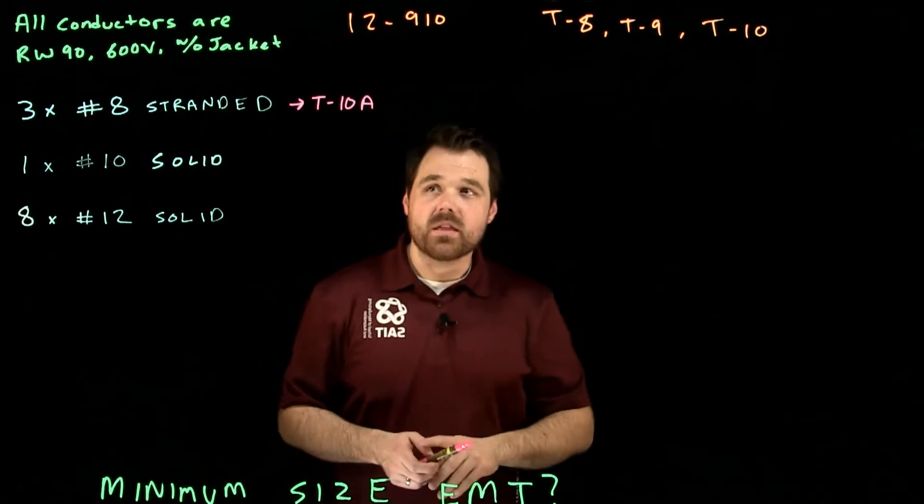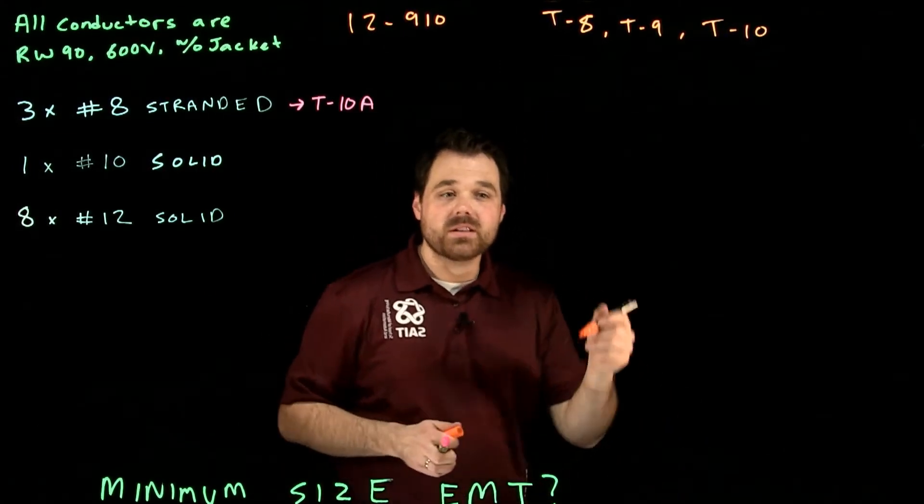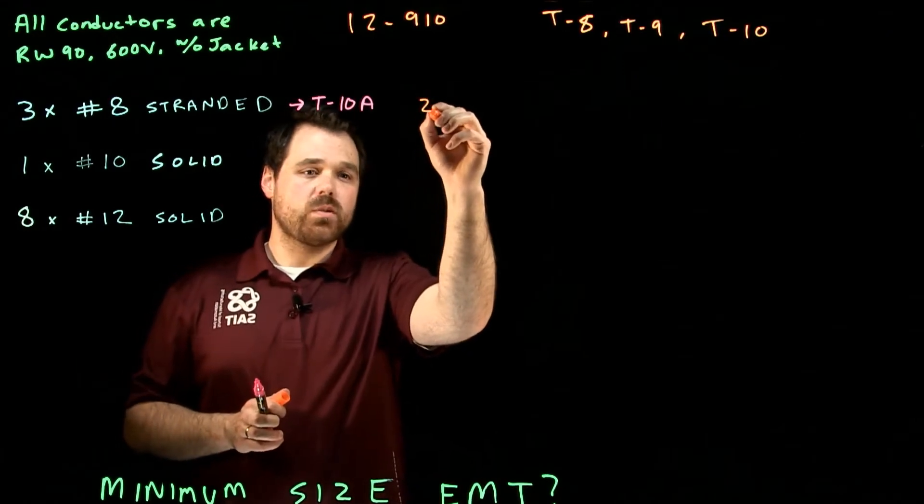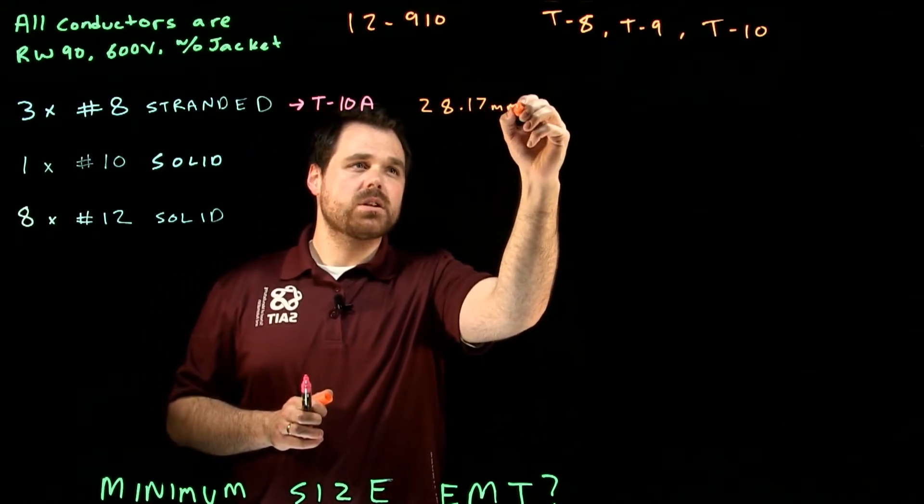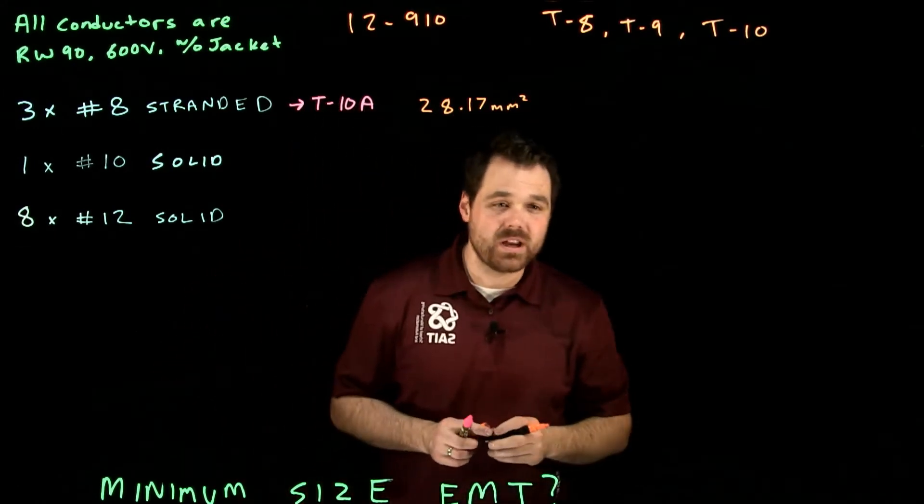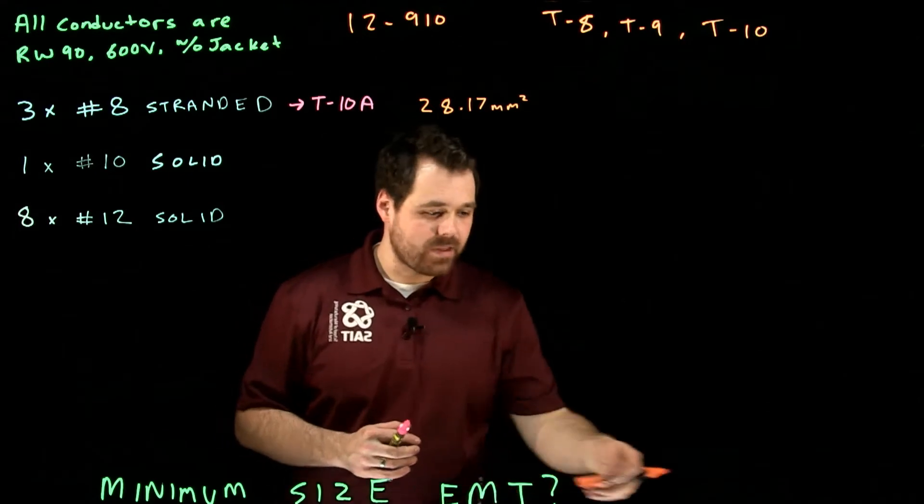And we are going to determine the size of one number 8. And we can determine that one number 8 is good for 28.17 millimeters squared. Now that's just one number 8. Yes, I know we're pulling three in the conduit, but we'll do that math after.